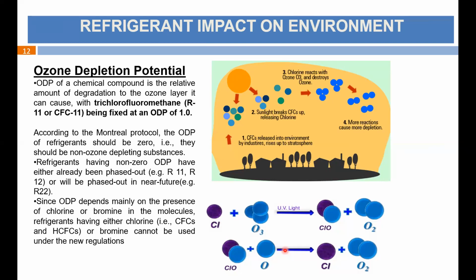Since ODP depends mainly on the presence of chlorine or bromine in the molecule, refrigerants having chlorine or bromine, chlorine in the case of all these Freons, cannot be used under this regulation. So what happens? CFCs are released into the environment by industries or any leakage from the refrigeration system. Then sunlight breaks the CFC up and releases the chlorine. This chlorine reacts with the ozone layer, O3, and destroys the ozone. The reaction takes place like this.